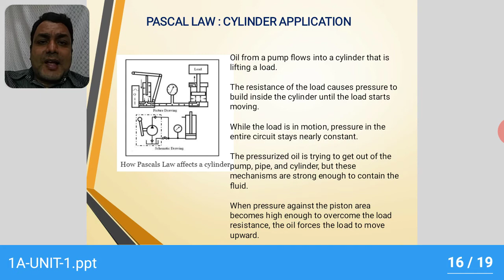So from the above application of a cylinder, two important things can be observed. First, the pump did not make any pressure, it only produced the flow. Pumps never make pressure, they can only give flow. Resistance to the pump flow causes pressure. This is one of the basic principles of fluid power that is of prime importance to troubleshooting hydraulic circuits. That means the flow will not make pressure, but the resistance to the pump flow causes the pressure which will move the load in the upward direction. This is the inherent principle of fluid power which we have studied by the example of Pascal's law.